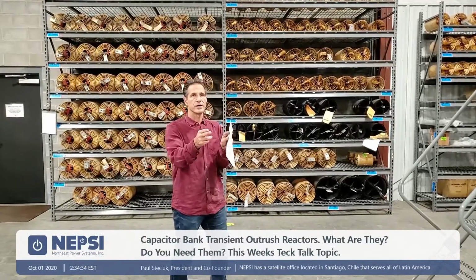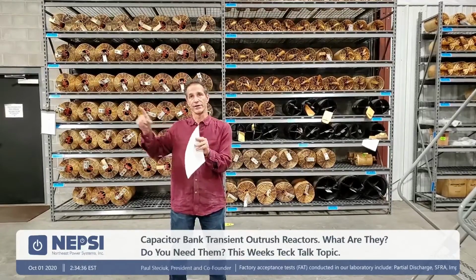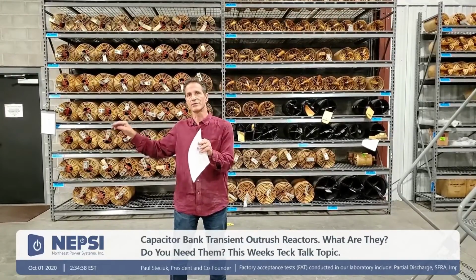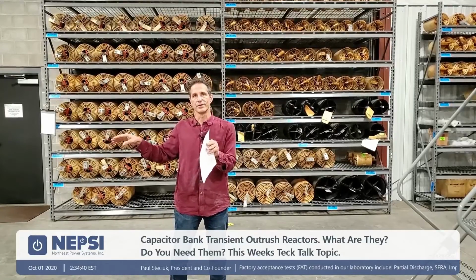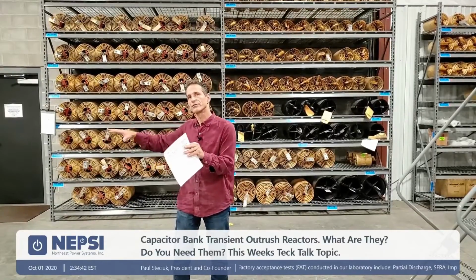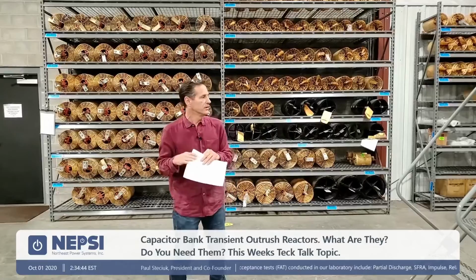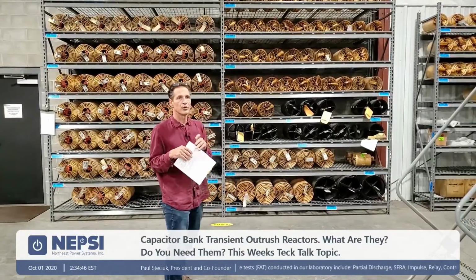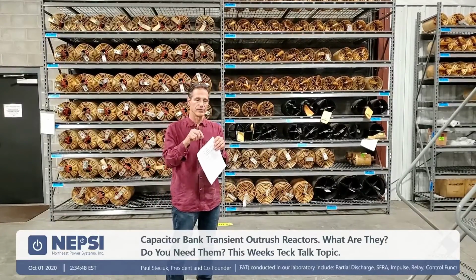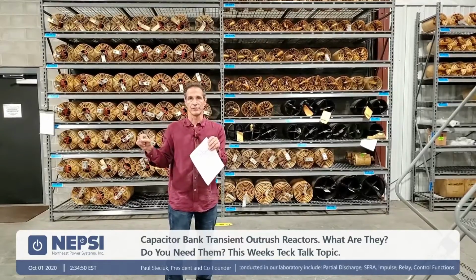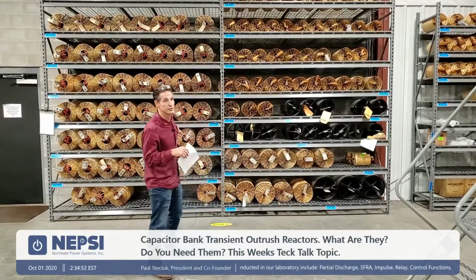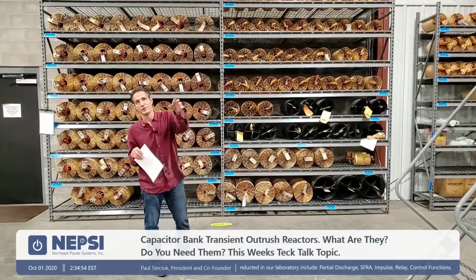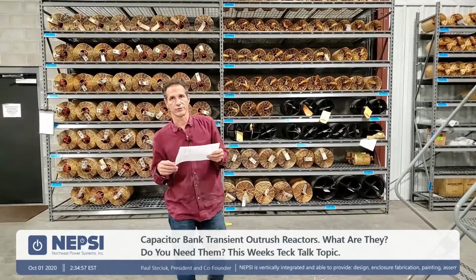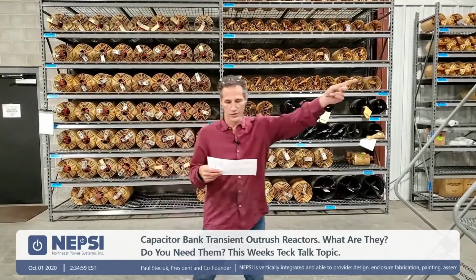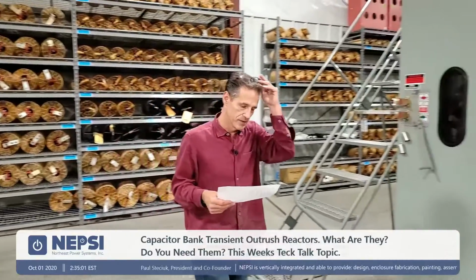The outrush reactors are designed for, again, the feeder breaker outside of the capacitor bank, those that feed the collector system within a wind farm. So think about that. It's the total impedance or total inductance from the capacitor bank to the location of the fault. So these transient inrush reactors will help to reduce the rating of the outrush reactors, which we're going to talk about in a moment. So let's just talk about this piece of equipment for a moment.